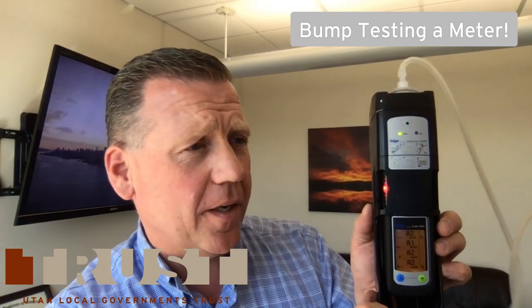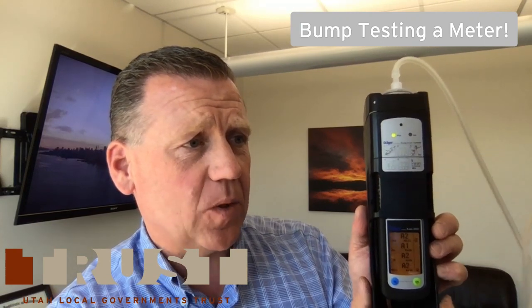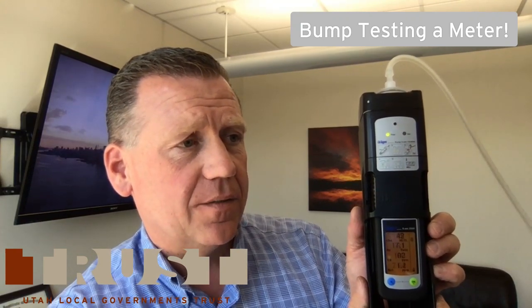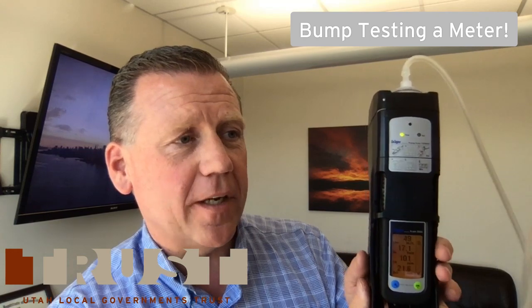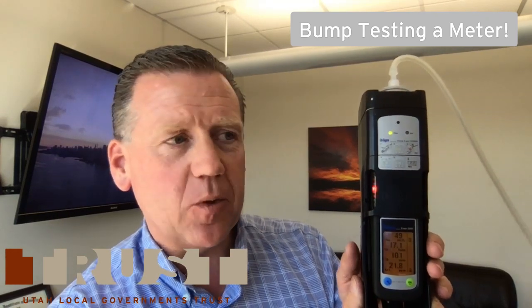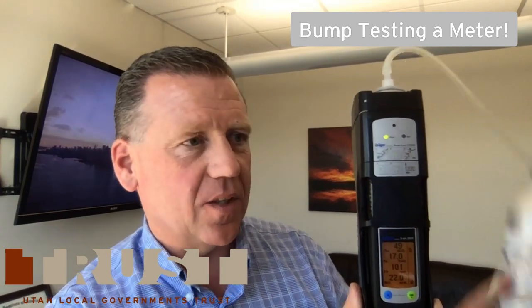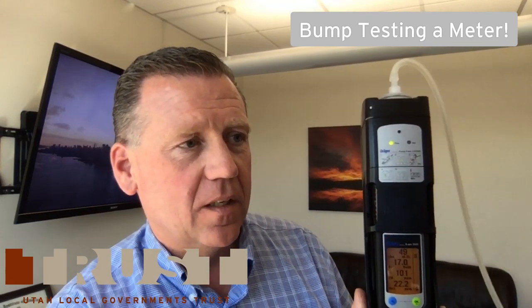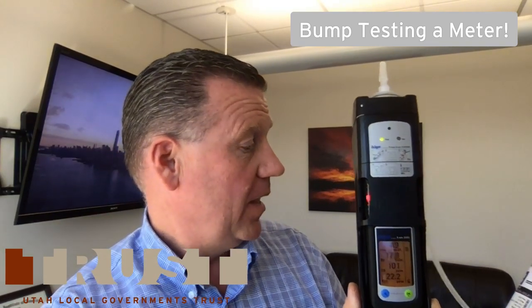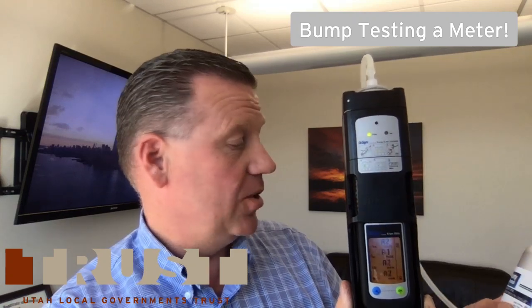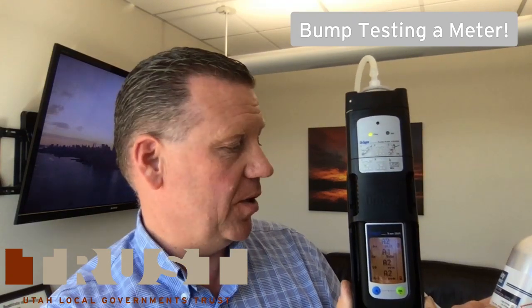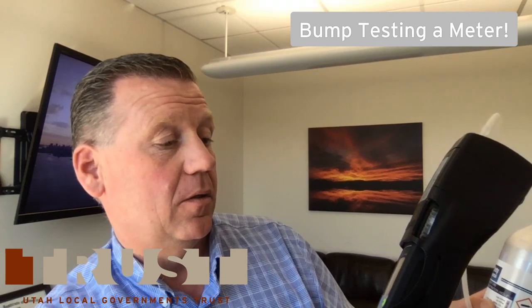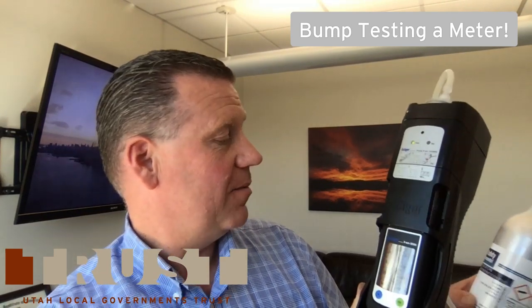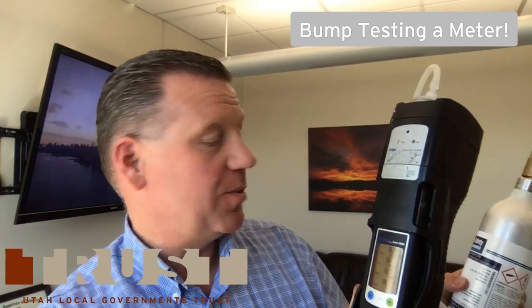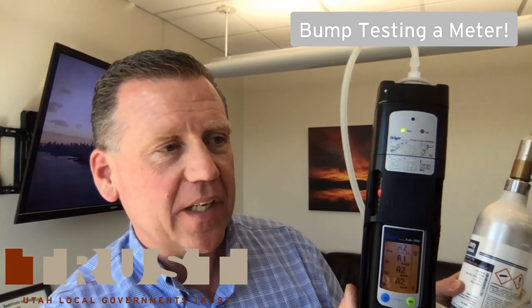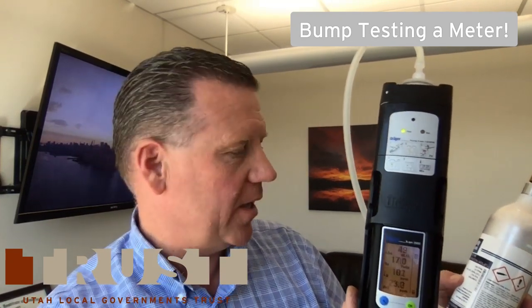And if I look on here, I can read those numbers. So you can see that top number. I'm at 49%. It should read 50%, because that's what it says on my bottle. My second alarm should be reading 25 parts per million. Oops, excuse me. No, I'm sorry, I was reading the wrong one. Oxygen should always be the first one. It's reading 17%. That's what it says on the bottle, so I'm reading right.